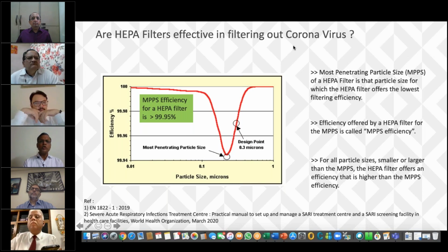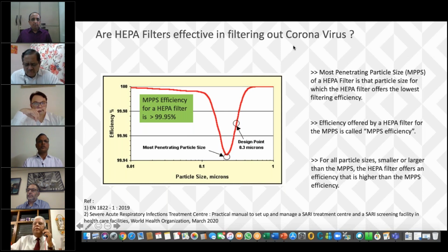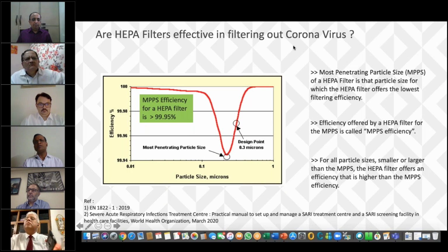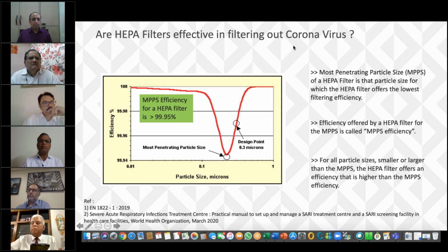So you will have a particular particle size for which the filtration efficiency of the filter is minimal, the lowest. For all other particle sizes, smaller or larger than this one, the efficiency would only be larger. And this is a classic characteristic of any HEPA filter, irrespective of make or brand. The HEPA filter has to behave like this if it was manufactured and tested properly. So the most penetrating particle size of a regular HEPA filter that we use in healthcare normally falls somewhere between 0.1 and 0.3 micrometers in size. And that is typically the size where we are also talking about this virus.